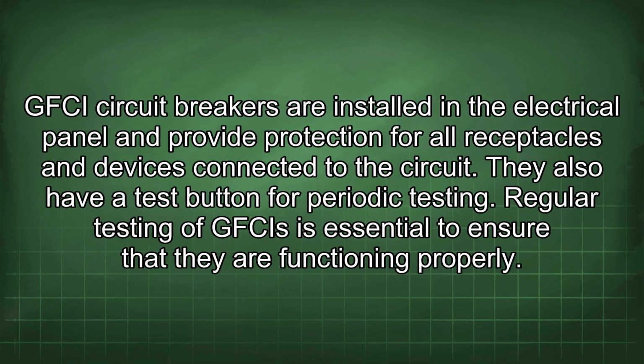GFCI circuit breakers are installed in the electrical panel and provide protection for all receptacles and devices connected to the circuit. They also have a test button for periodic testing. Regular testing of GFCIs is essential to ensure that they are functioning properly.